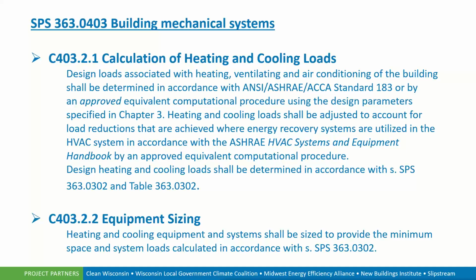403.2.1 talks about the calculations of heating and cooling loads. Okay. So it's required that you meet ANSI/ASHRAE/ACCA Standard 183 or an approved equivalent formula or procedure, but it all comes back to the tables with the outdoor design temperatures that we showed earlier in section 303. The equipment shall be sized to provide the minimum sized equipment to meet the loads anticipated. So no oversizing of equipment, making sure that we get that minimum system calculation, again in accordance with the heating and cooling temperatures in the earlier chapter.